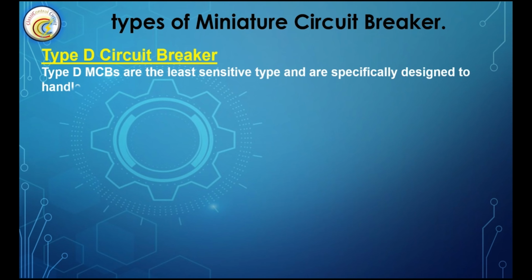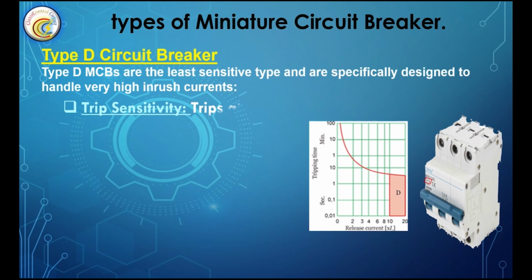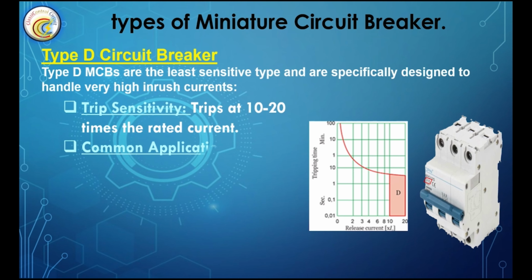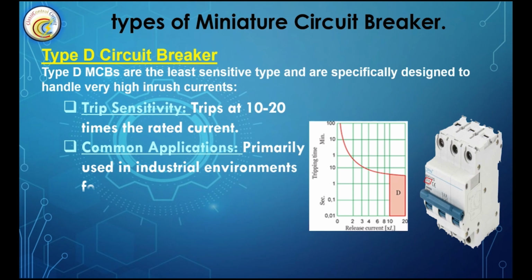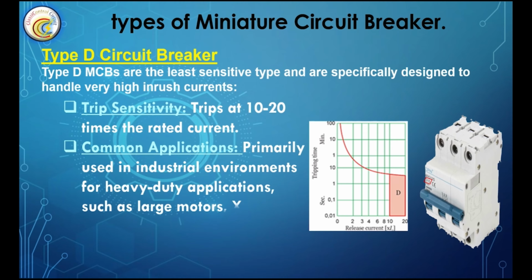Type D circuit breaker. Type D MCBs are the least sensitive type and are specifically designed to handle very high inrush currents. Trip sensitivity: trips at 10 to 20 times the rated current. Common applications: primarily used in industrial environments for heavy-duty applications, such as large motors, X-ray machines, and welding equipment, where high starting currents are expected.